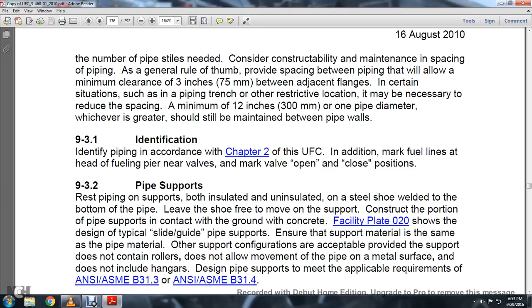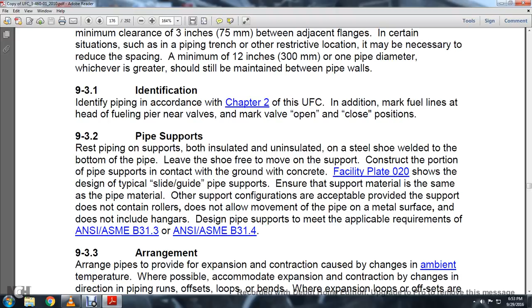Other support configurations are acceptable, provided the support does not contain rollers, does not allow movement of the pipe on a metal surface and does not include hangers. Design pipe and supports to meet the applicable requirements of ANSI/ASME B31.3 and ANSI/ASME B31.4.